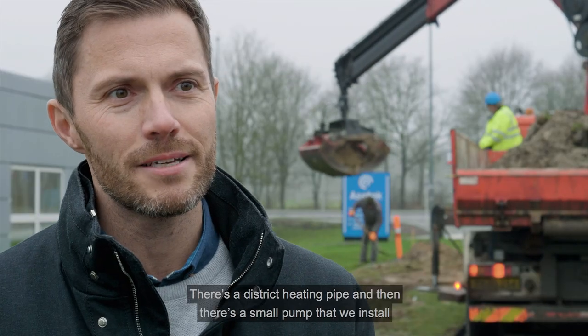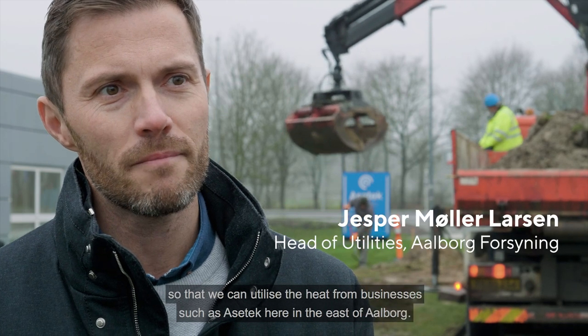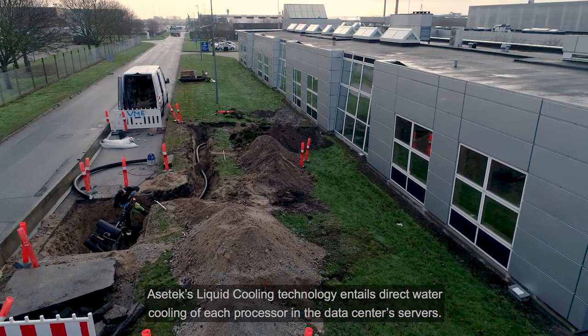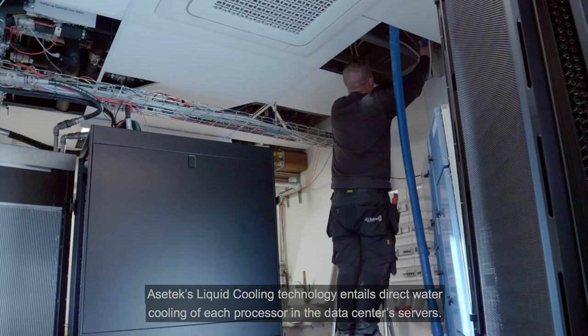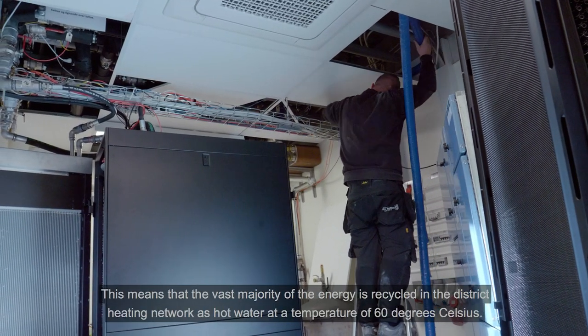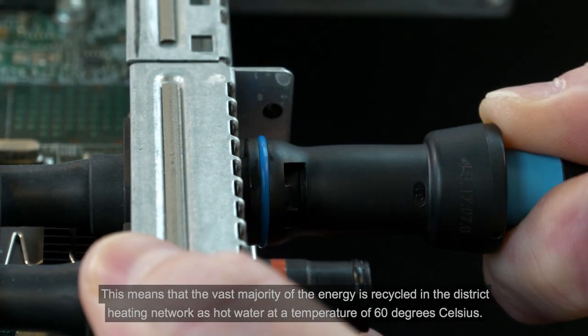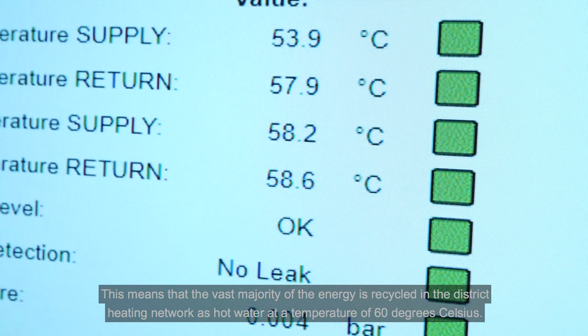It's very simple. It's a small pump we put on, so we can use the heat from a company like Asetek here in Aalborg. Asetek's liquid cooling technology entails direct water cooling of each processor in the datacenter's servers. This means that the vast majority of the energy is recycled in the district heating network as hot water at a temperature of 60 degrees Celsius.